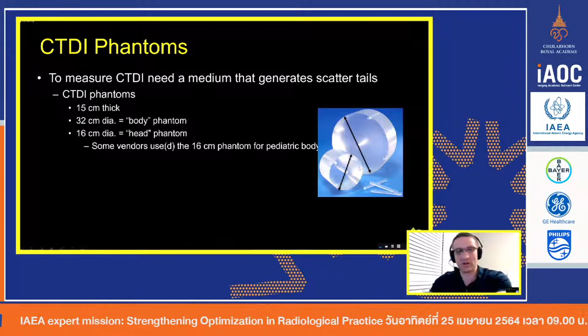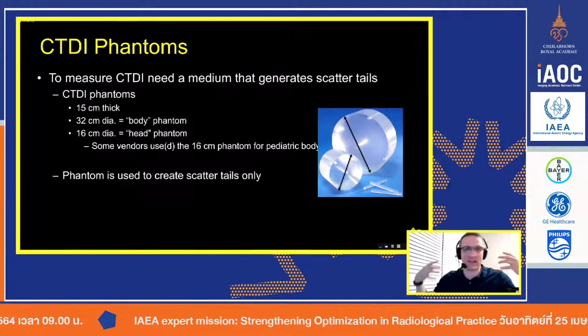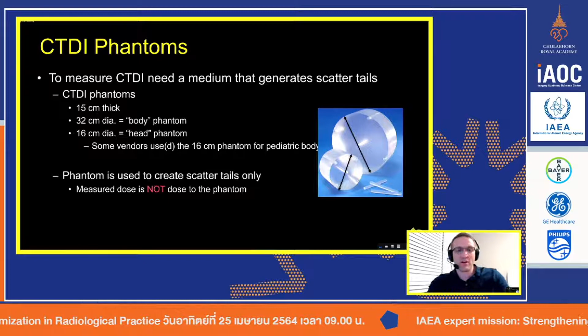We need the phantom because we stick the ion chamber in any one of these holes to make the air kerma measurements, but our bodies create a lot of scatter, as we talked about, backscatter from the skin, etc. Our bodies generate a lot of scatter as the radiation enters it. So we use these phantoms to try to mimic that same kind of scatter environment. All right, so a couple of things to point out. When we're calculating CTDI, we're actually not calculating dose to the phantom. It's actually dose to air. It's air kerma. We only use the phantom to create scatter, and it's at the center.